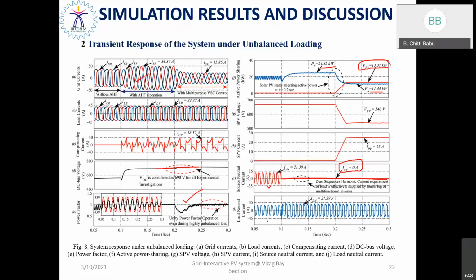And still the load neutral current is circulated, but we do not worry about the load, we are more concerned about the utility grid. So how do we neutralize the third harmonic current presence in the utility grid? We use the fourth leg of the inverter. Please remember that.